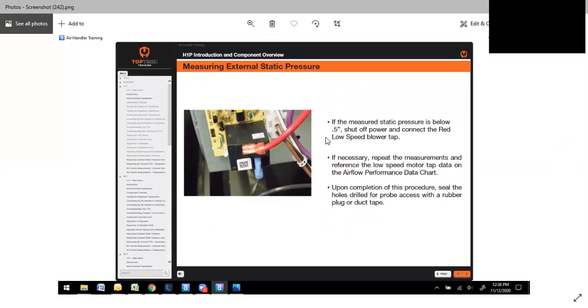So in this case, if the measured static pressure is below .5, you can go ahead and drop down to the red, the low speed tap. If necessary, repeat the measurements and reference low speed motor tap data on the chart. Upon the completion of this process, seal up the holes. You can use whatever you want to, little silver tape, those little snap-in divots, whatever you need to do.